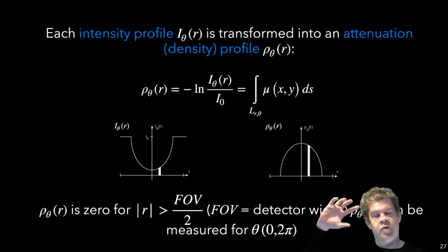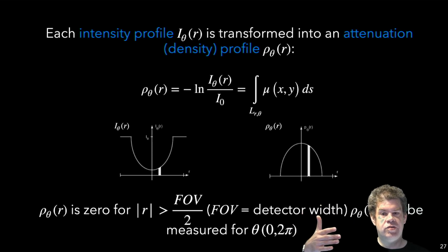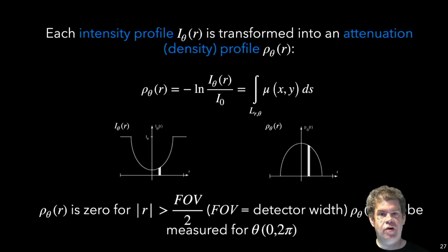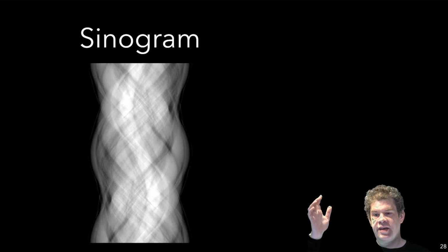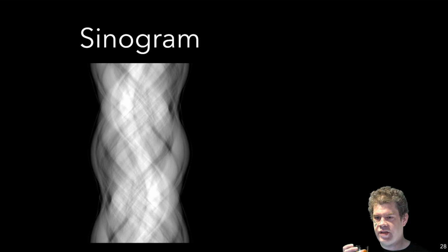So what does this mean? Well, what we get in the measurement is the intensity, how much X-ray is there, and we just turn this into attenuation by saying, okay, well, how much is lost, how much is blocked, okay? Because that's what we ultimately want to know. We don't really care about how much radiation made it out. We care about what exactly was blocked, okay? So this is the first type of transformation that we generally do, and it's this logarithm computation that I mentioned before. So what that gives us is this here, and that is an original result. That's the output of a CT scanner.